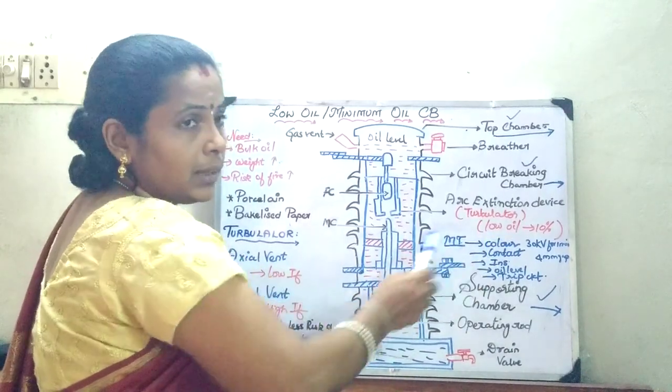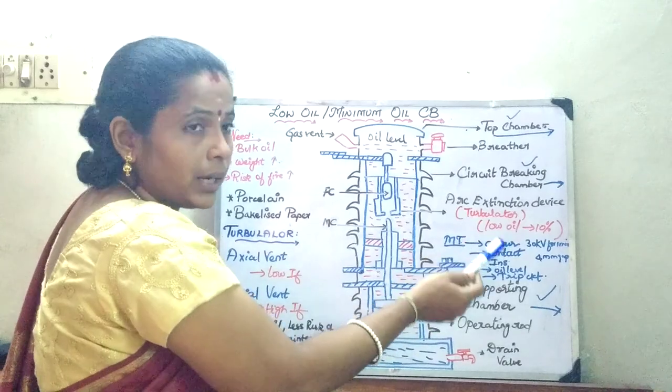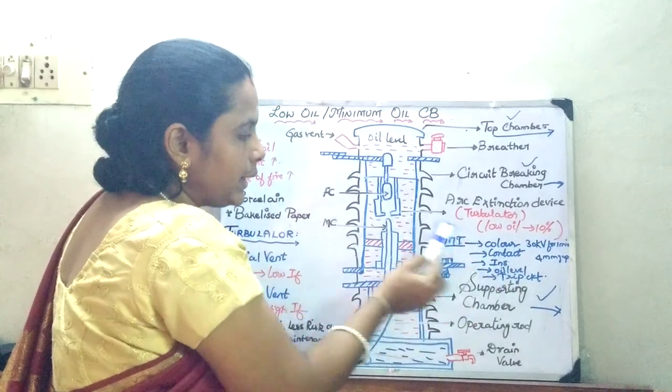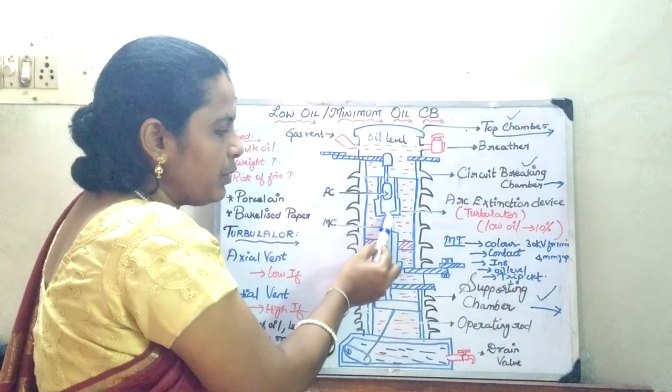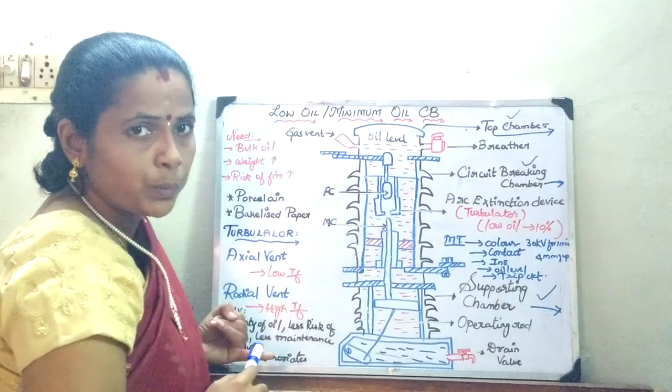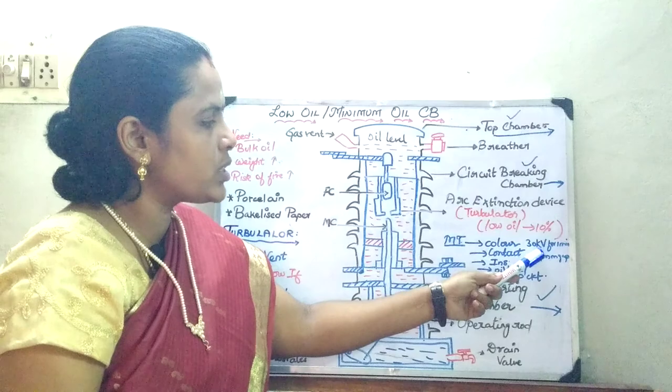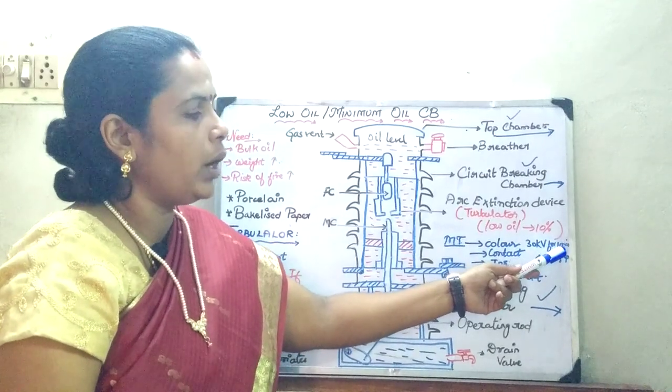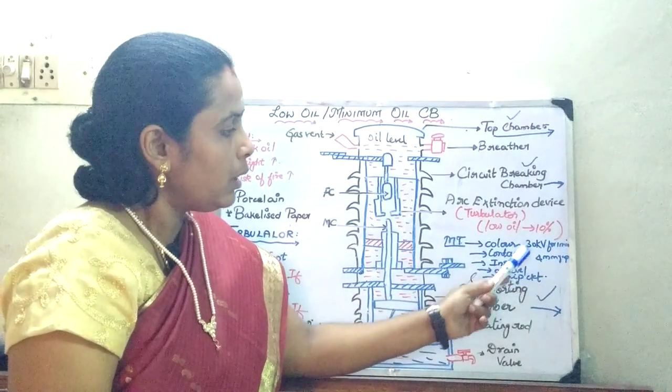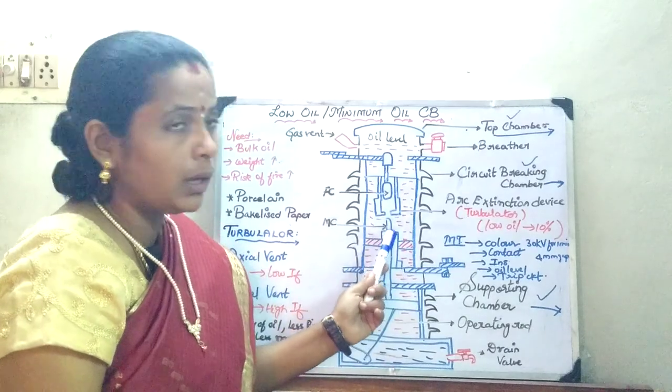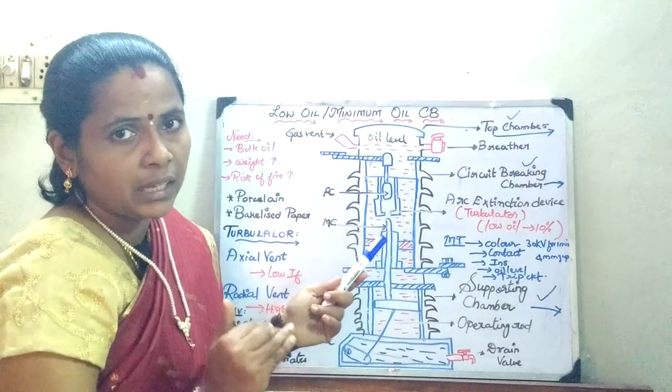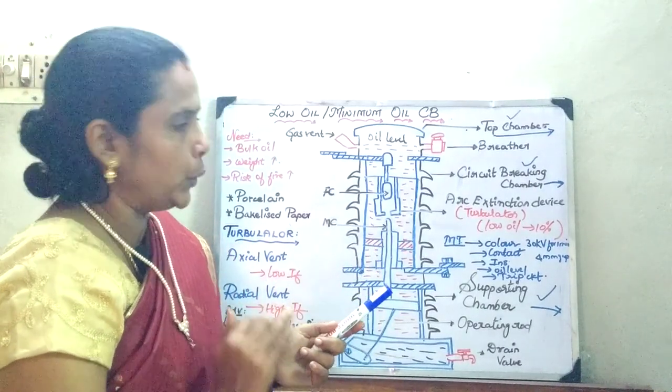With respect to its color, the color will change, the odor will change, and the contacts may burn. So the contacts should be checked regularly. And you should check whether the oil is able to withstand 30 kV for 1 minute for a 4 mm gap between the electrodes. If that is the case, the quality of the oil is good.